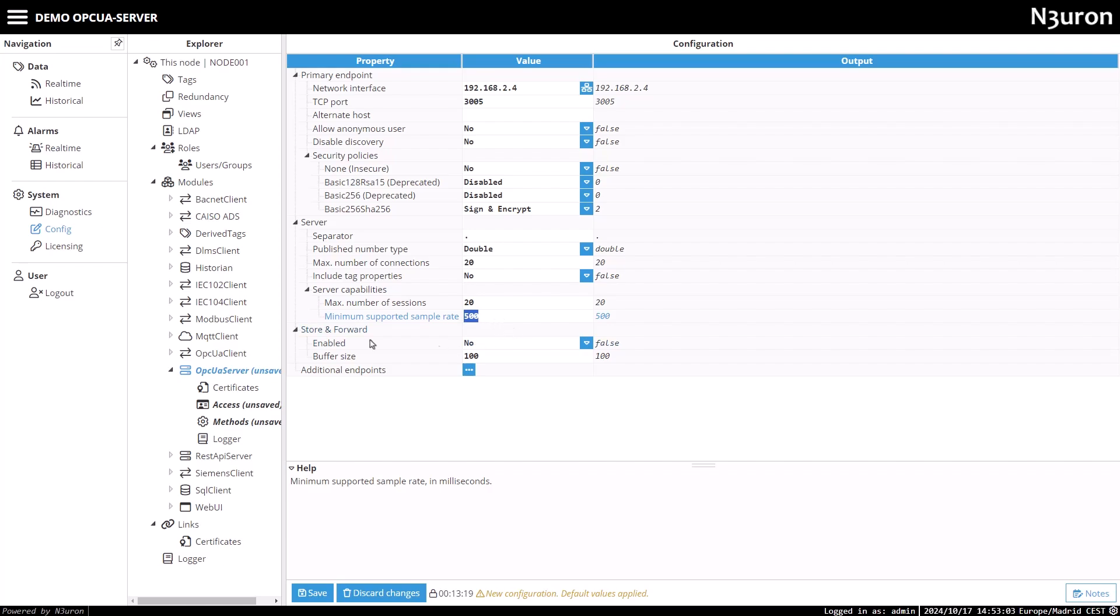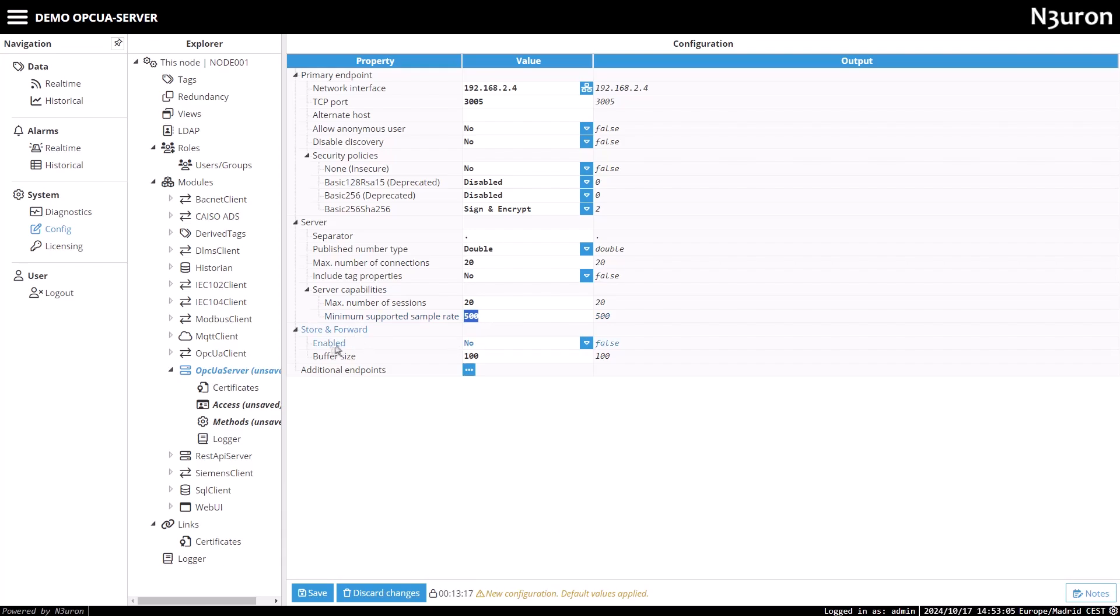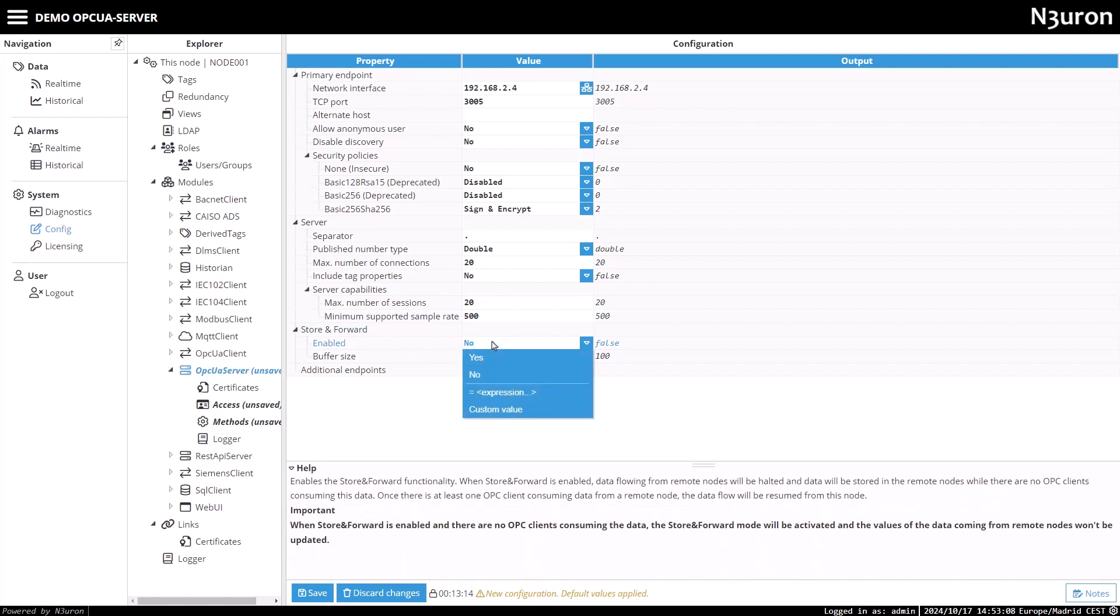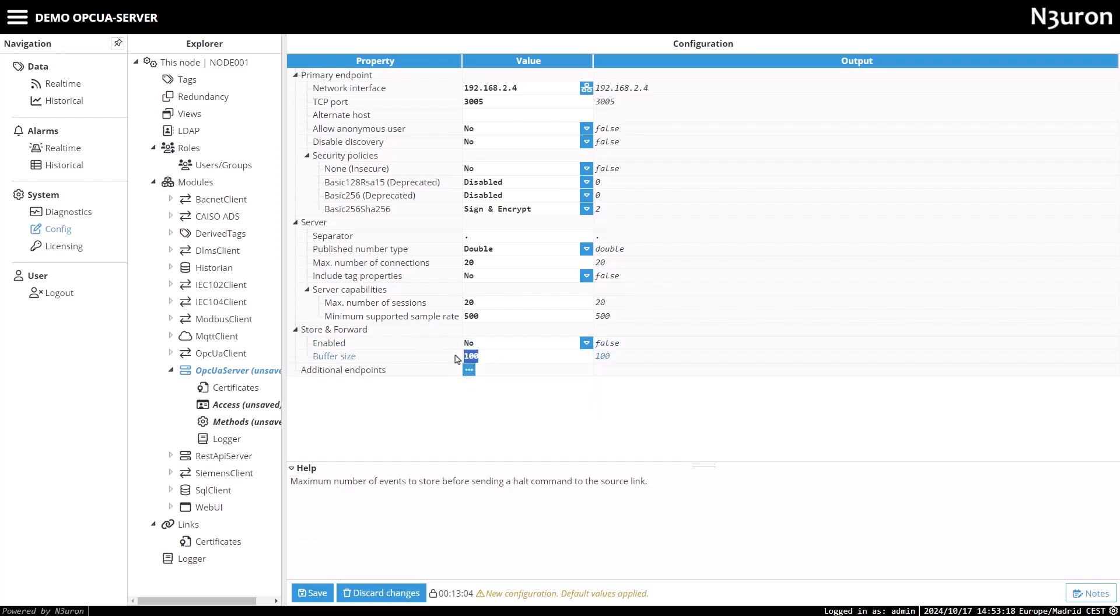Now, let's navigate to the store and forward settings. When this option is enabled, data from remote nodes is stored if no OPC clients are active, pausing transmission. Data transmission will resume as soon as a client starts consuming data. The buffer size determines the maximum number of events to store before halting the source link.